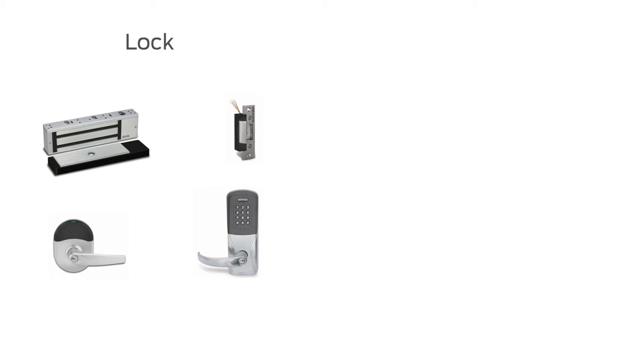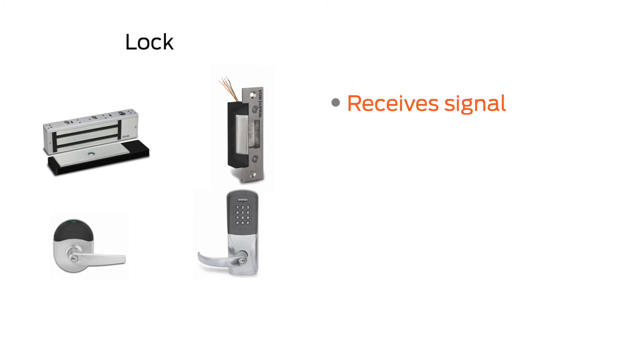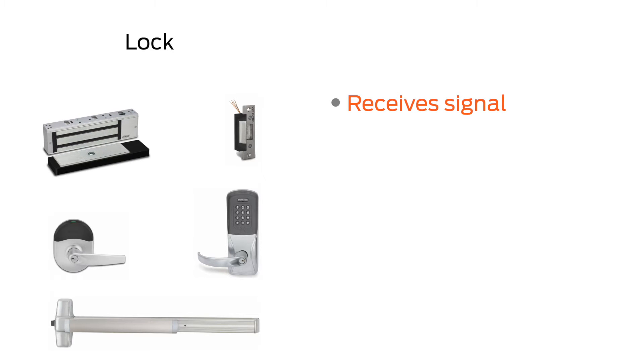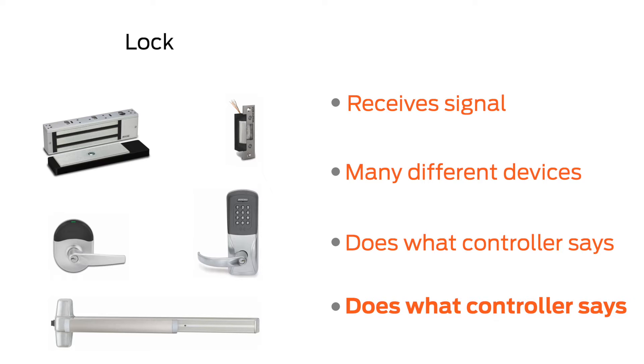If all of the checks the controller has been programmed to do pass, then the controller will send a signal to unlock the door. The lock is the part that receives the signal from the controller and unlocks. It might be a lock you're familiar with — with levers and a latch — or it might be an electric strike, a magnetic lock, or an exit device. Good access control systems can support sending unlock signals to a variety of them. The locking device's job is pretty simple: do what the controller says — unlock, lock, beep, flash a red or green light. The locking device doesn't perform any electronic function unless explicitly told to by the controller, and it doesn't know anything about the reader, the person getting in, or even what time it is. It just follows commands from the controller.